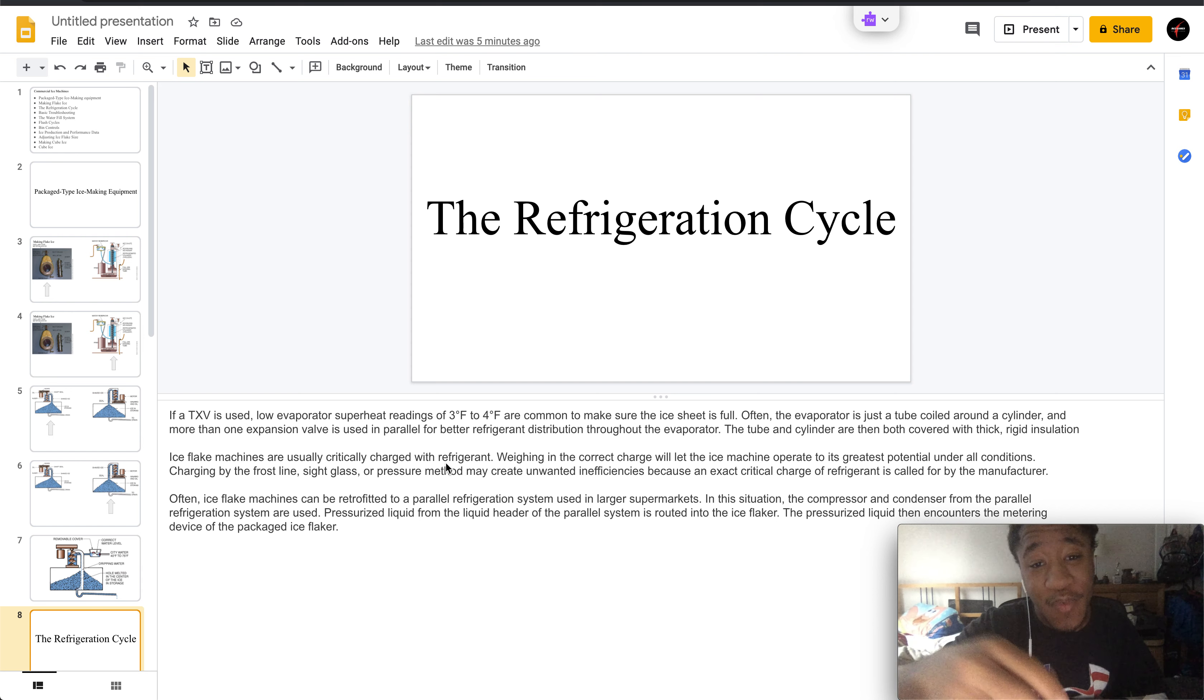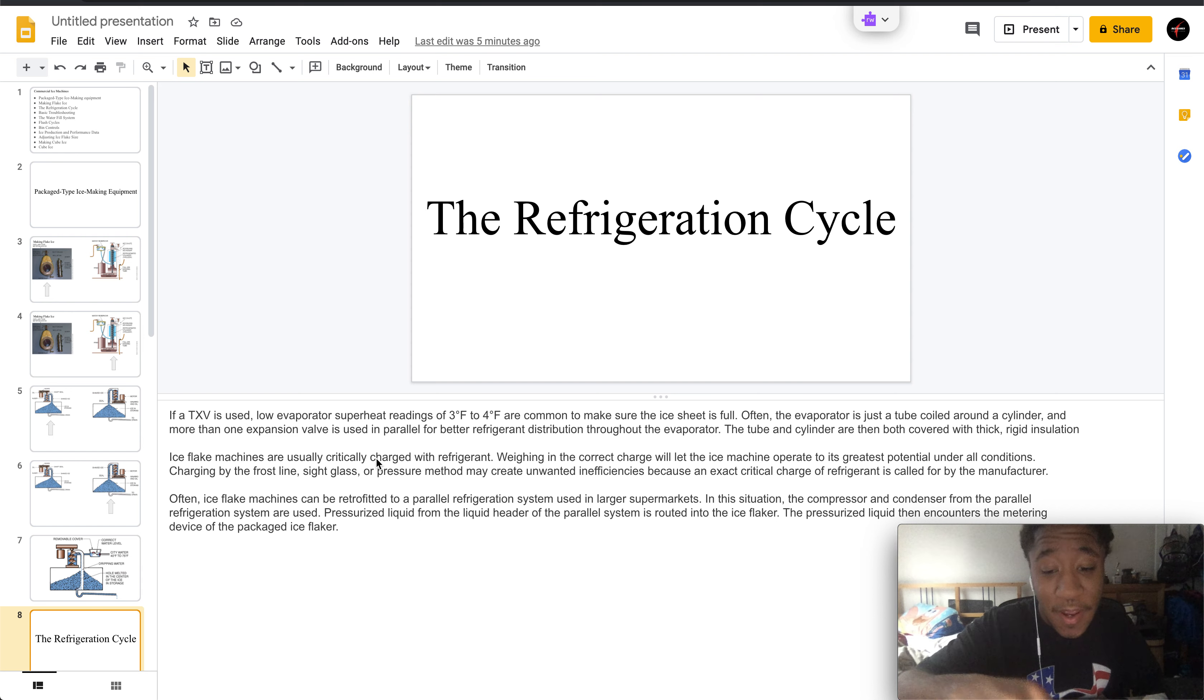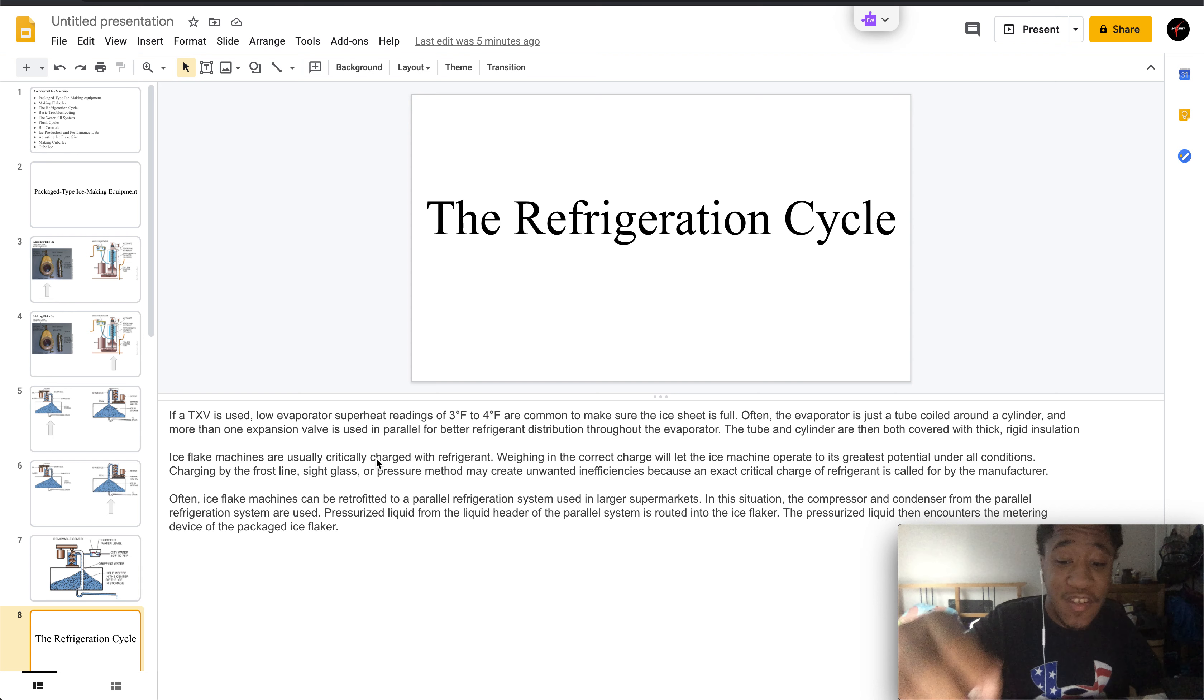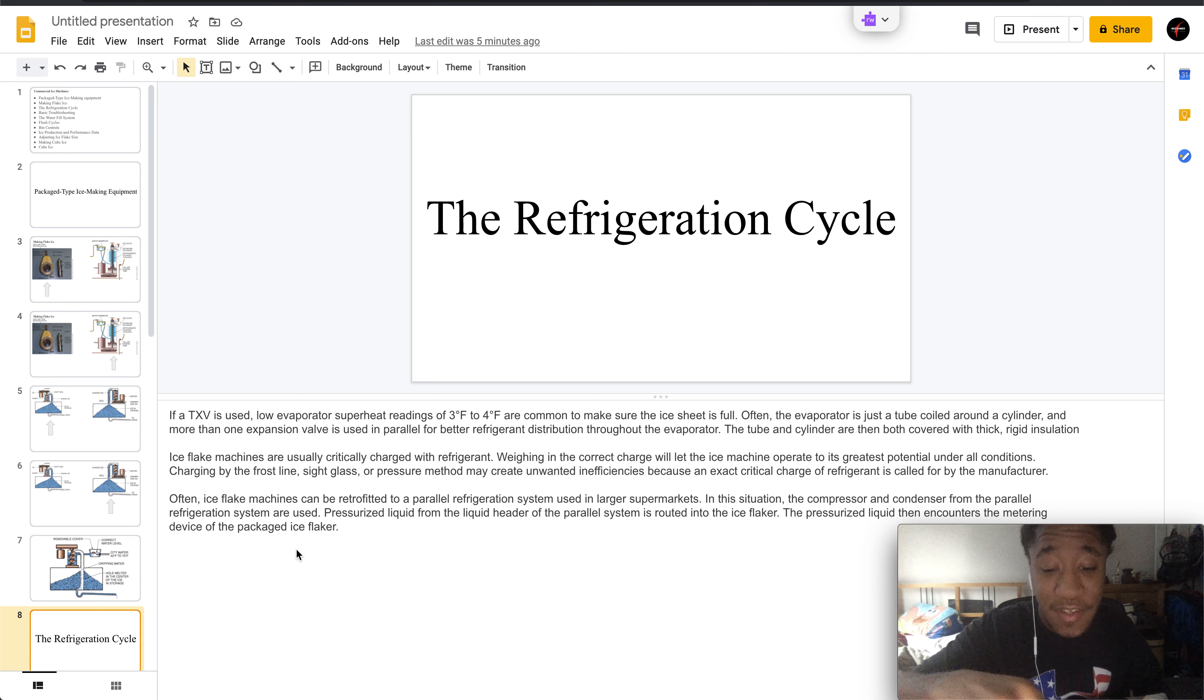The tube and cylinder are both covered with thick rigid insulation. Ice flake machines are critically charged with refrigerant, which is weighed in the correct charge. This will let the ice machine operate to its greatest potential under all conditions. Charging by the frost line sight glass or pressure method is going to create unwanted inefficiencies.